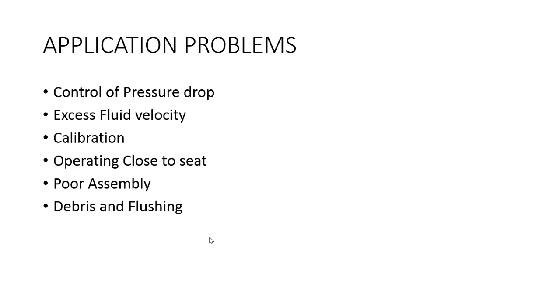The problems of erosion, noise, cavitation, and flow instability can be eliminated by considering the fluid velocity. Due to high velocity, there can be vibration which can cause excessive wear, breaking parts, unscrewing bolts, and noise. If the noise level exceeds 110 dBA, then the shock waves can also break the pipe. Due to cavitation and flashing, rapid corrosion can also occur. The outlet velocity must be limited as per this table. We have to follow the table and stay within this limit.